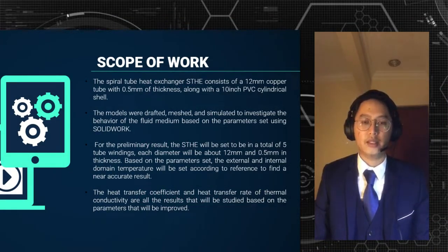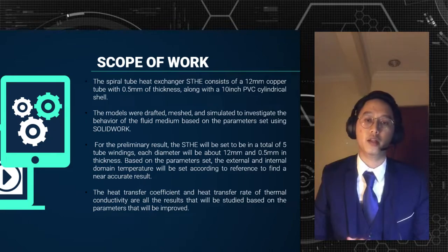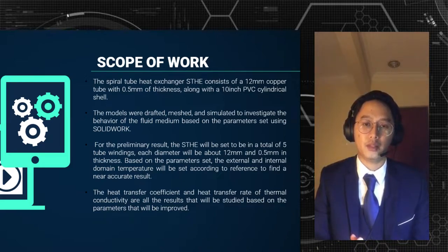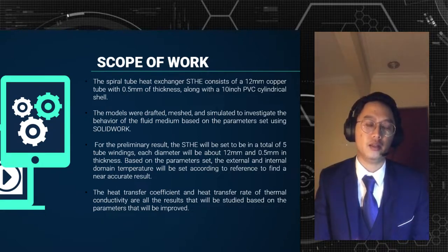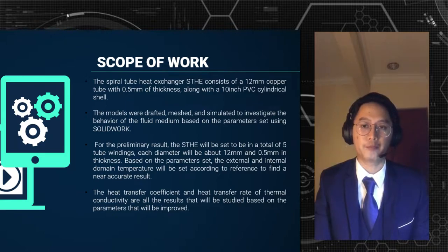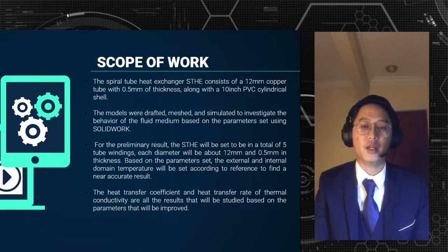Moving on to the scope of work, it is a rough overview of the design mechanism of the spiral tube heat exchanger. The product will consist of a 12 mm copper tube with 0.5 mm thickness inside a 10-inch diameter PVC cylindrical shell. The model will be drafted, meshed, and simulated using SOLIDWORKS software, with a preliminary setup of 5 tube windings. The internal and external domain temperatures will be set based on the design reference for a near-accurate result.